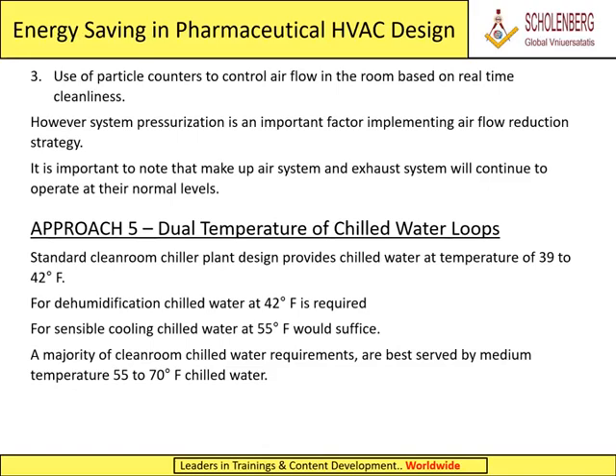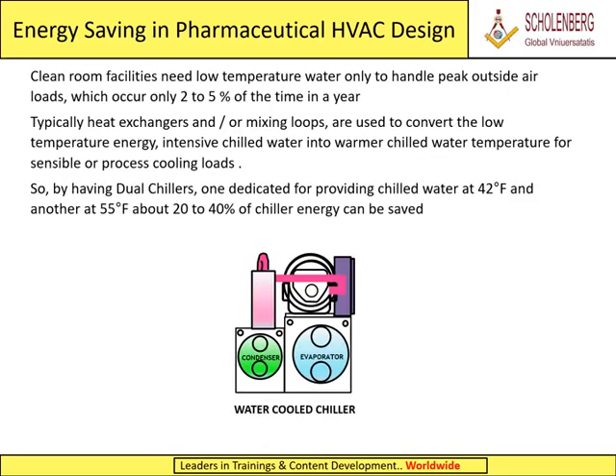Approach 5. Dual temperature chilled water loops. Standard cleanroom chiller plant design provides chilled water at a temperature of 39 to 42 degrees Fahrenheit. For dehumidification, chilled water at 42 degrees Fahrenheit is required. For sensible cooling, chilled water at 55 degrees Fahrenheit would suffice. A majority of cleanroom chilled water requirements are best served by medium temperature, 55 to 70 degrees Fahrenheit, chilled water. Clean room facilities need low temperature water only to handle peak outside air loads, which occur only 2 to 5% of the time in a year.